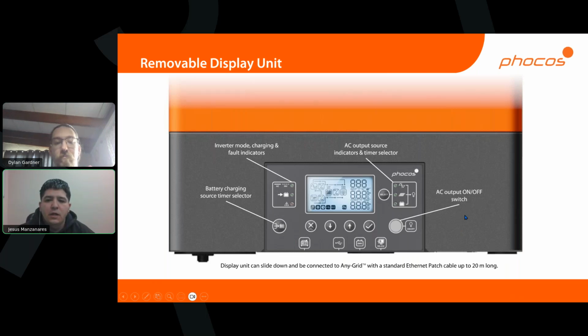So just so you can see, this is our display here that is completely removable. And we have light indicators to see what our AC priority is and what our inverter mode is, whether it's charging, or working off AC or battery. You can also set a priority and a battery charging timer, and select whether you want to charge from solar or from PV at a specific time. And then there's an AC output on and off switch here as well. You can see we have an RS-232 communication cable where we would connect our AnyBridge to communicate with the inverter itself. You also have BMS if you were to have any other battery communicate directly, as well as where you connect the genset relays underneath.